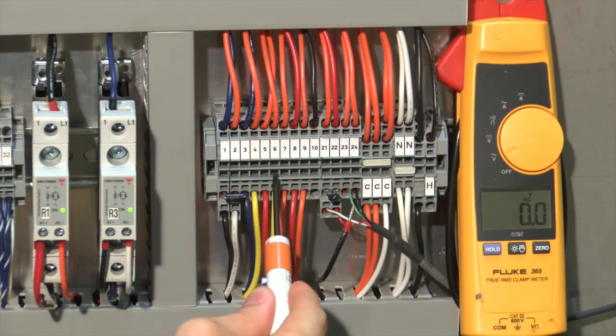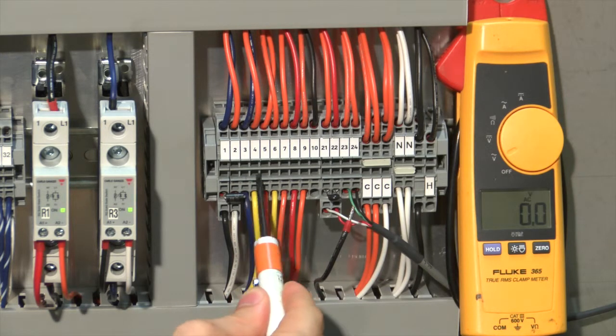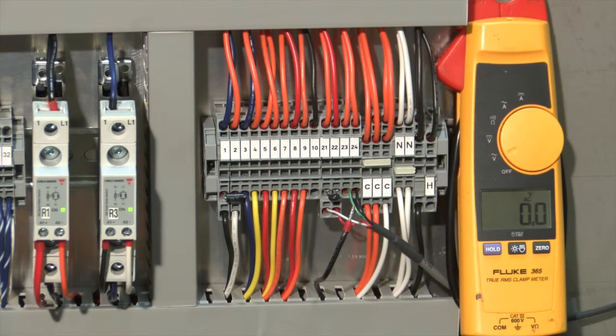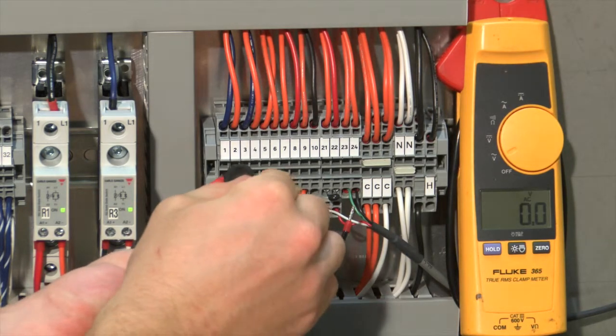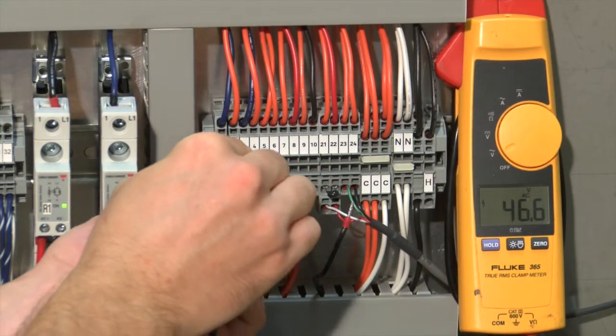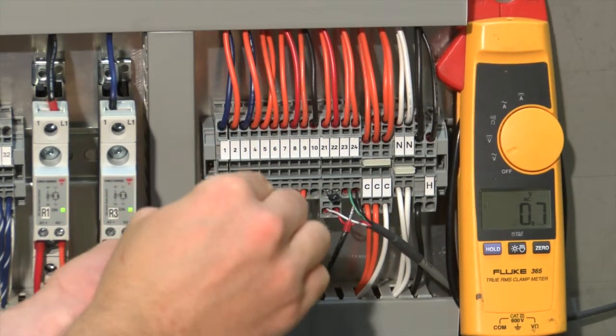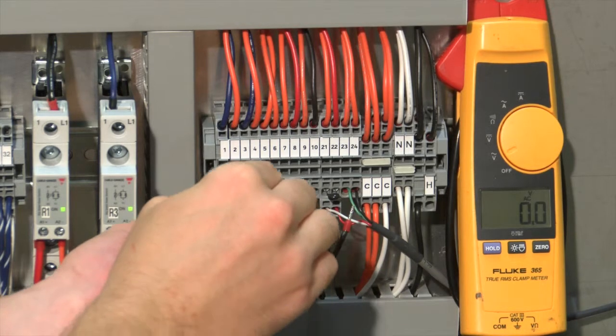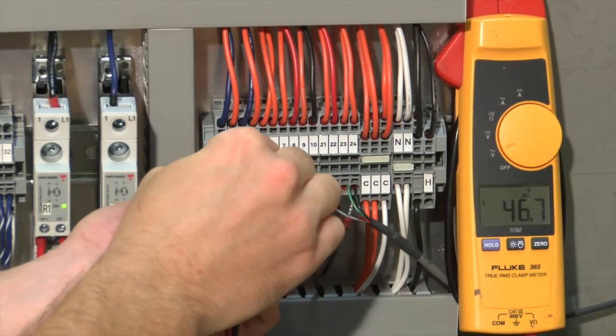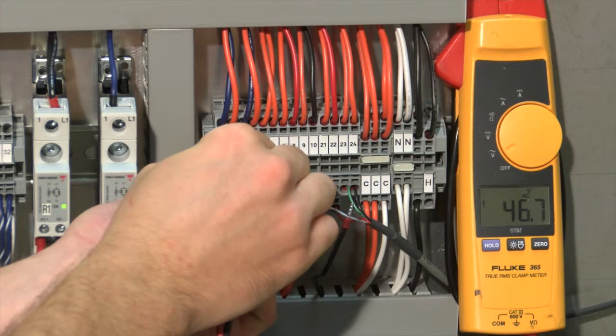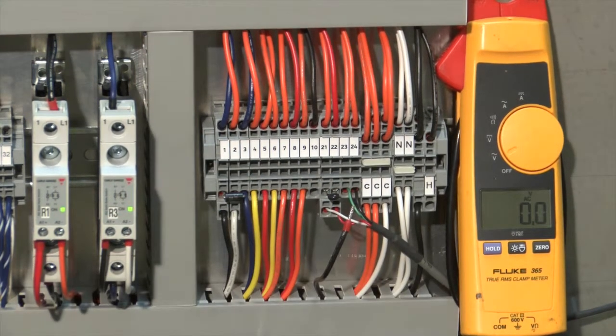The small openings in the middle of the terminal blocks are used to make contact with the circuit. Having your voltmeter set on AC, we can take a reading at terminal 1 and 2 and see our 48 volts. We can take a reading at 3 and 4 and see our 48 volts for row B. If these terminals are powered by 48 volts and your transducers are still not operating, the transducers themselves may have failed.